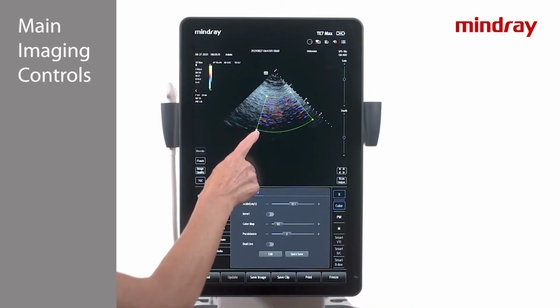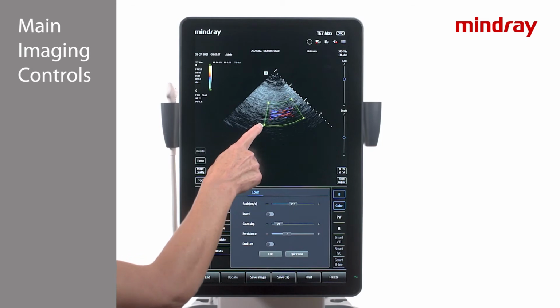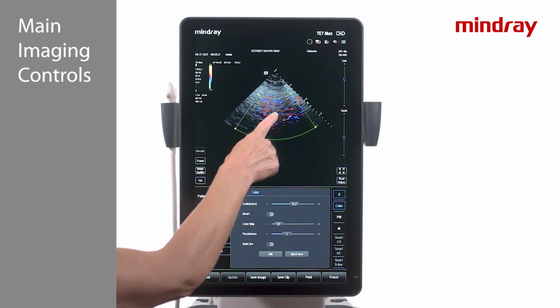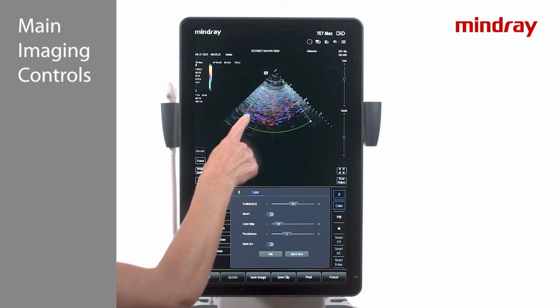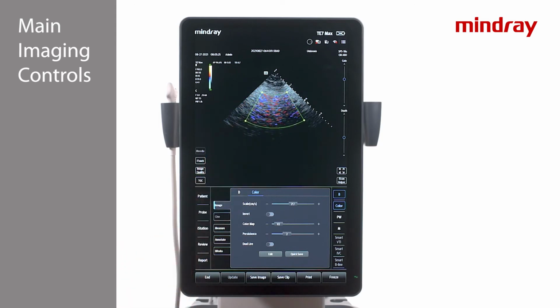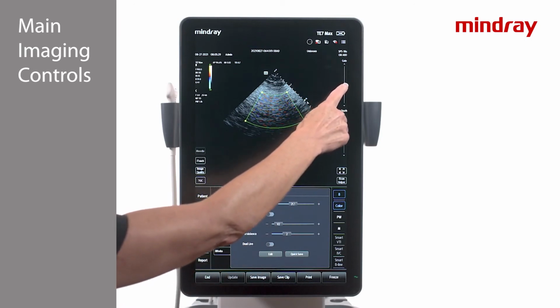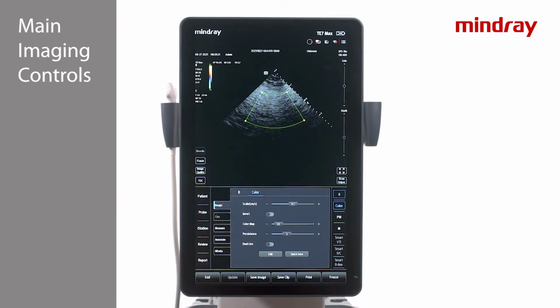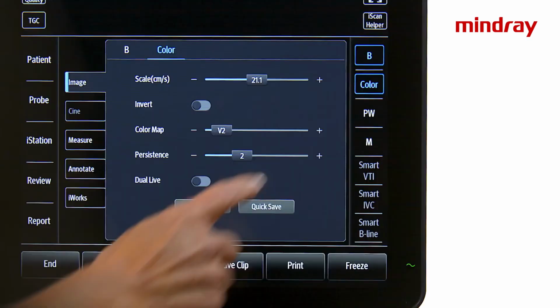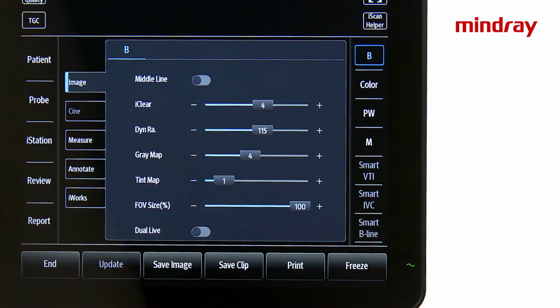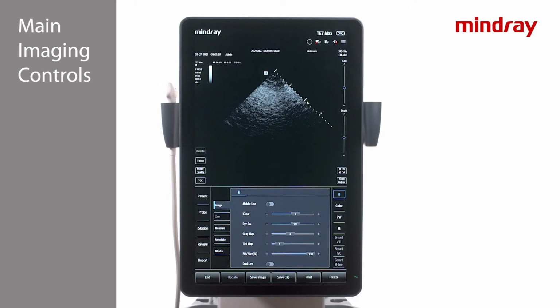To change the size of the color box, tap and drag one of the dots in the corner of the color box. To change the position of the box, press a finger in the middle of the box and drag it around the image. Notice, while in color mode, the gain works to increase and decrease your color gain. To exit color mode, either press the Color key again or press the B key just above it.